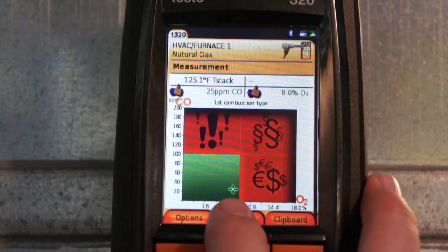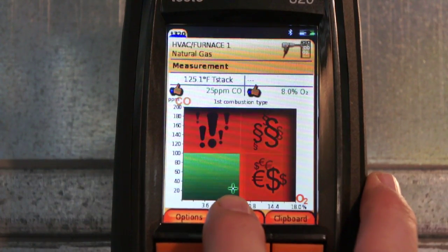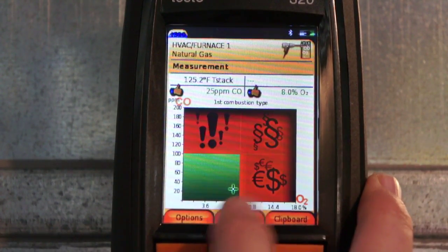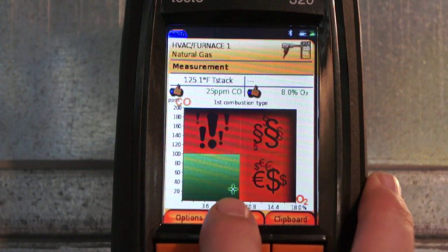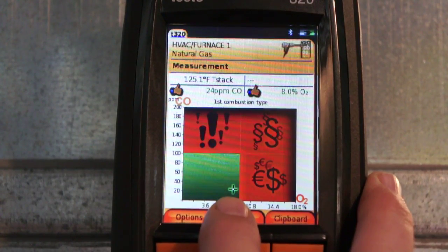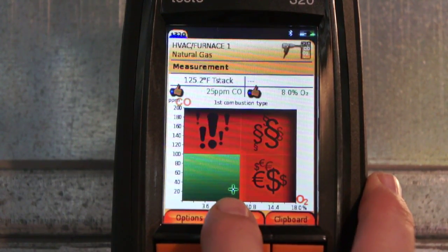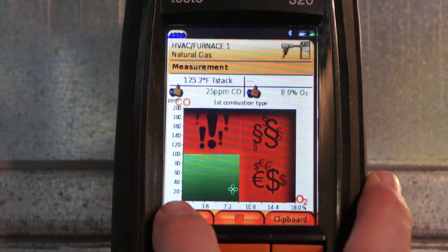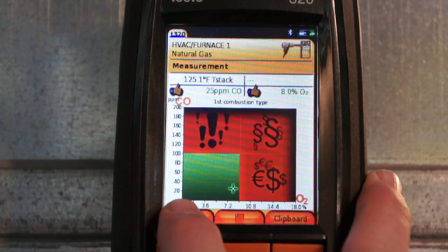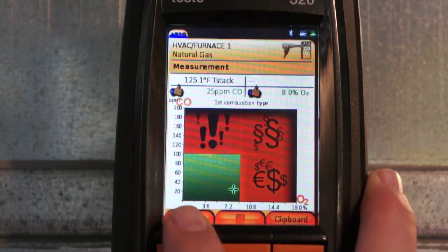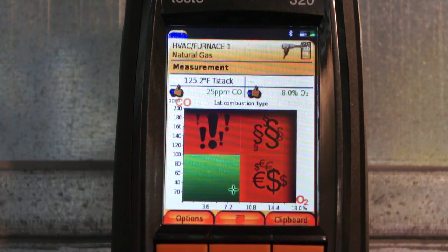While we're in the safe zone, as far as CO and O2 are concerned, you do have to keep in mind that we do want to maintain about 50% excess air on this 90% efficient appliance. So don't let the fact that this green zone goes all the way down to 0% fool you, because we want to make sure that we still have enough excess air for safe combustion and enough excess air that as the appliance gets dirty, it doesn't start to make CO.